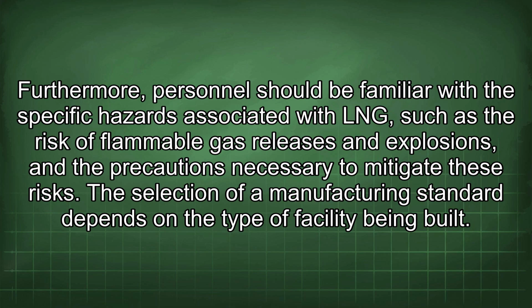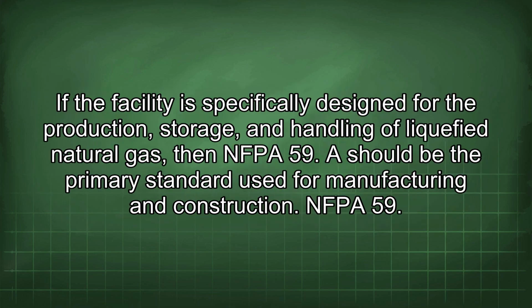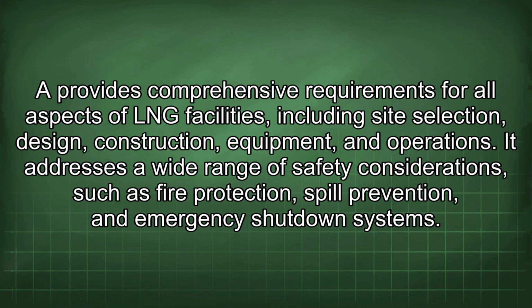The selection of a manufacturing standard depends on the type of facility being built. If the facility is specifically designed for the production, storage, and handling of liquefied natural gas, then NFPA 59A should be the primary standard used for manufacturing and construction. NFPA 59A provides comprehensive requirements for all aspects of LNG facilities, including site selection, design, construction, equipment, and operations. It addresses a wide range of safety considerations such as fire protection, spill prevention, and emergency shutdown systems.